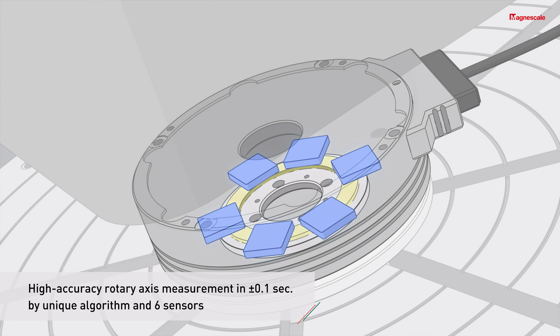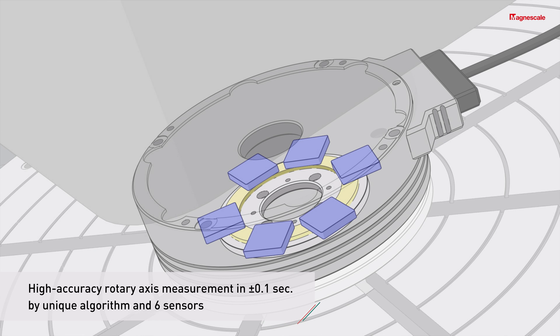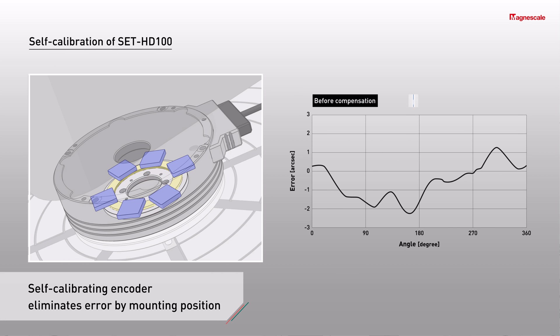SET-HD100 uses 6 sensors and unique algorithms for self-calibration, to compensate angular errors for the entire circumference within ±0.1 seconds. And this accuracy is traceable in accordance to Japanese Measurement Standards JCSS.